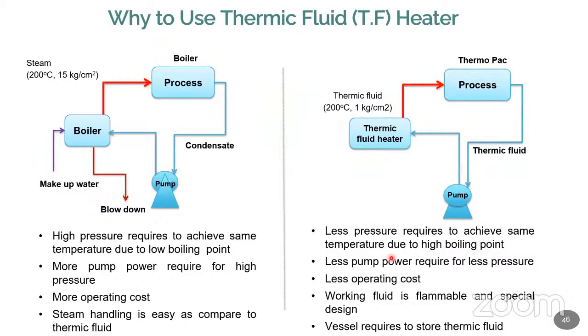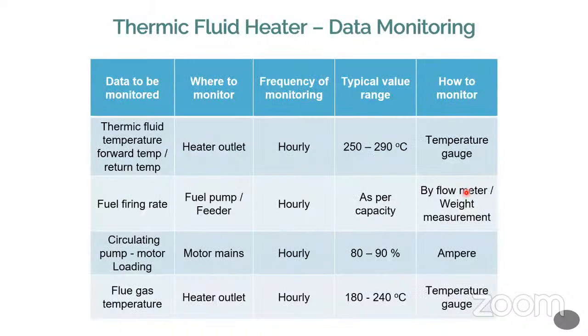Now you can see the TFH. In the TFH, less pressure is required to achieve the same temperature due to the higher boiling point. The boiling point is very high, so low pressure is required. So only one pump or fewer pumps are required. You need only one pump to feed the oil to the heater. Because of that, the operating cost is very much lower. And the vessel required to store the thermic fluid is the only additional cost, not the others. The working fluid is flammable, and you have a special design for heating up the oil.